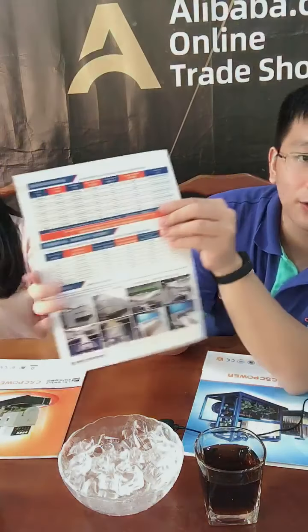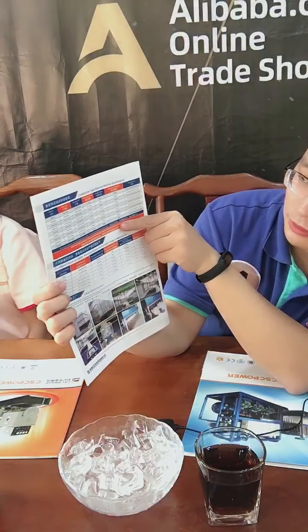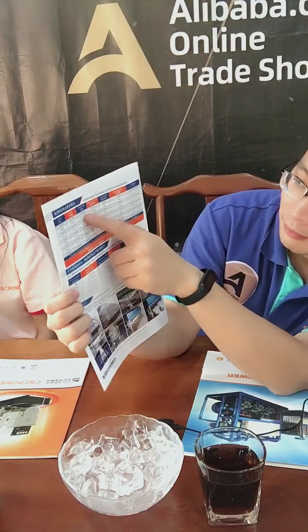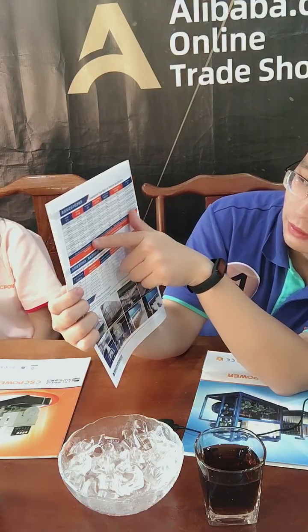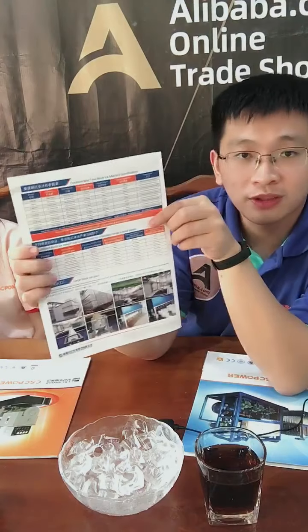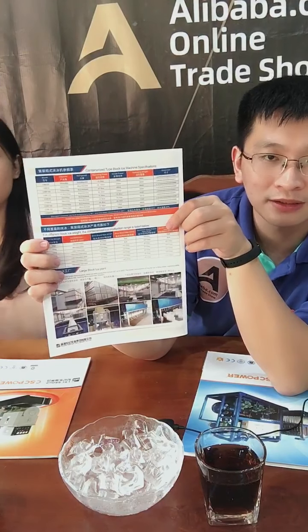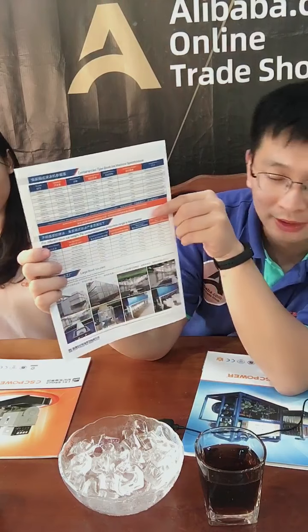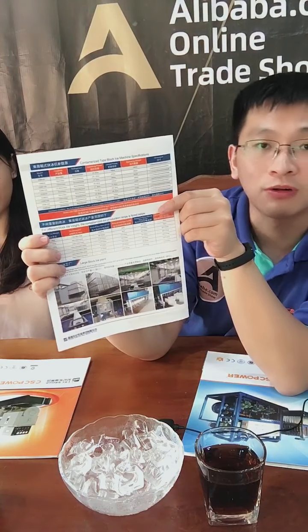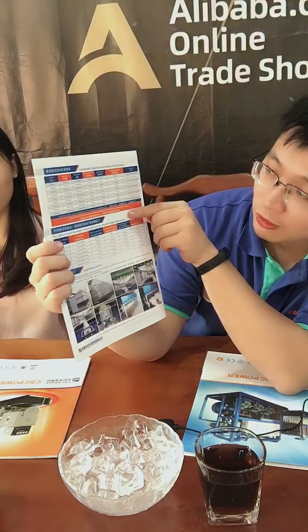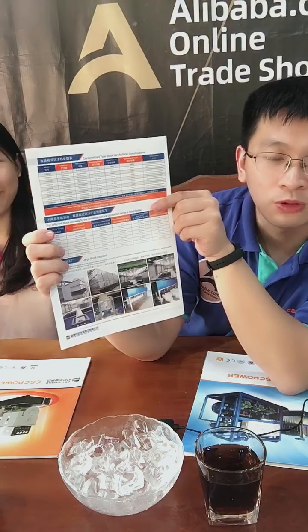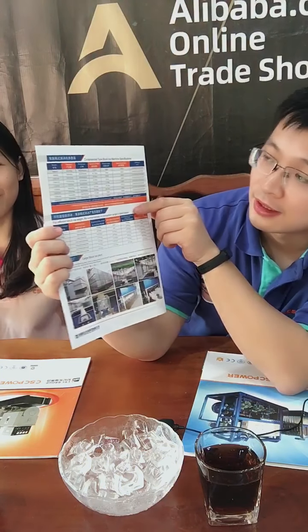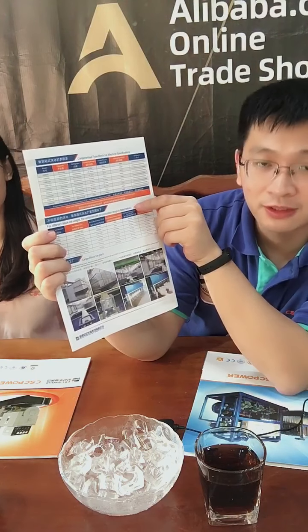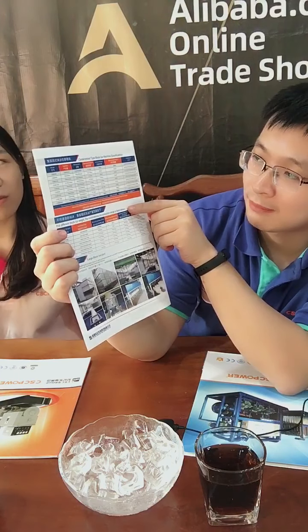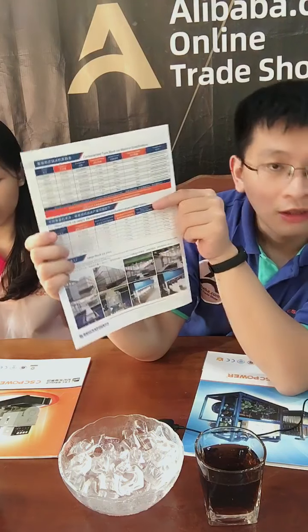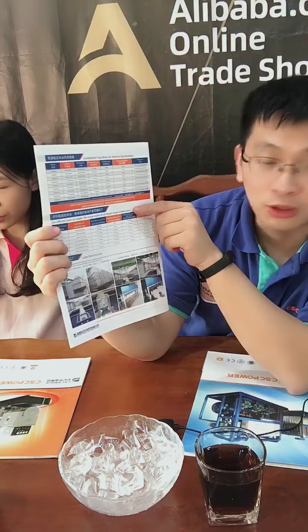This is the specification for the brine type block ice machine. It can make 3 tons to 20 tons. Normally, for a 20-feet container, the biggest brine type ice machine capacity is 5 tons, which is the biggest capacity to load in a 20-feet container. For a 40-feet container, we can make around 10-ton block ice machines or a little bigger.